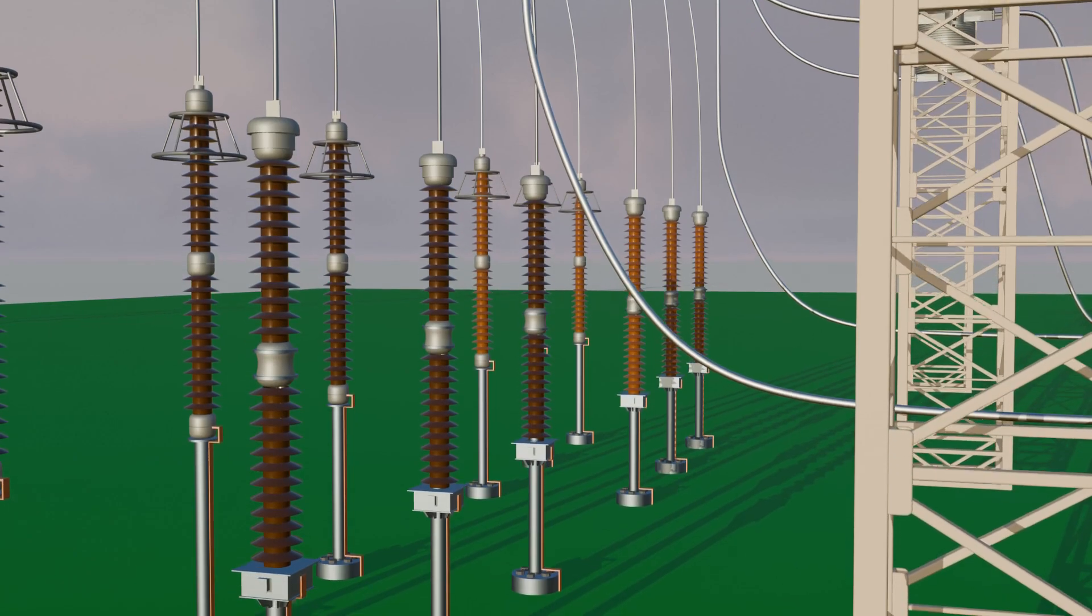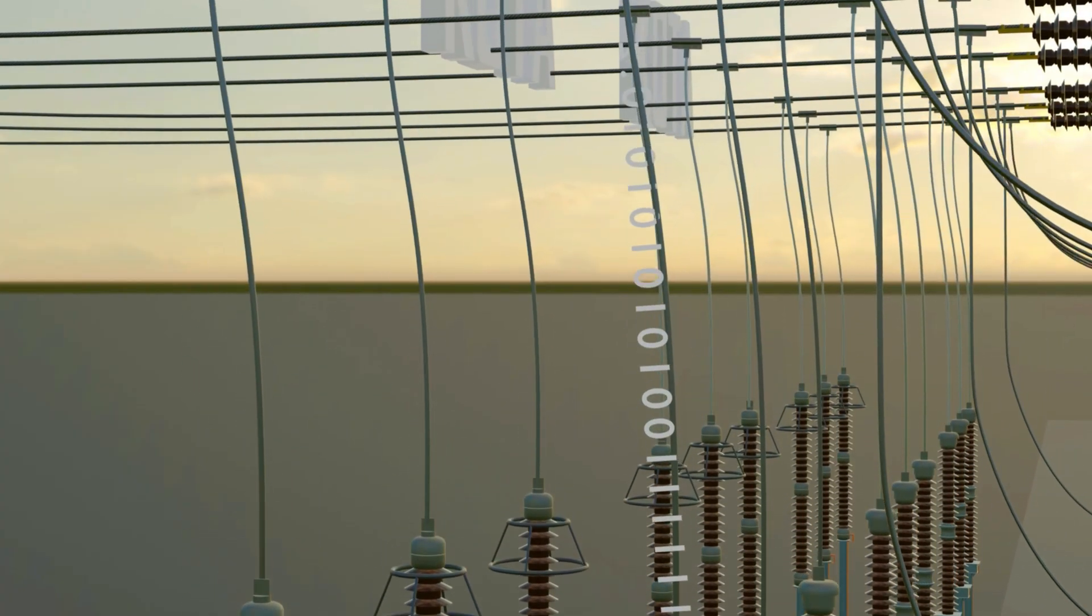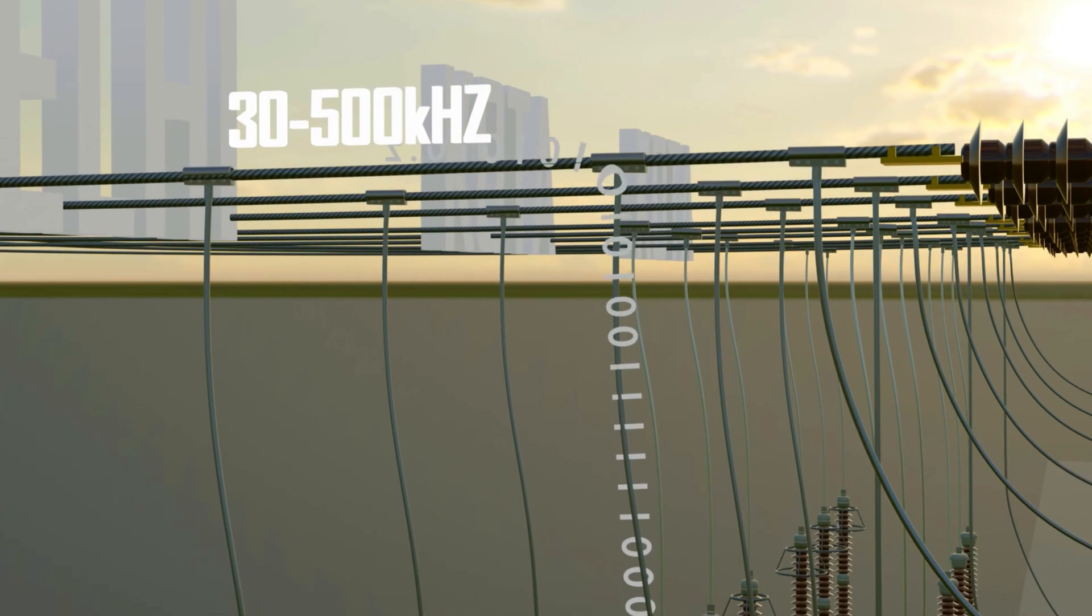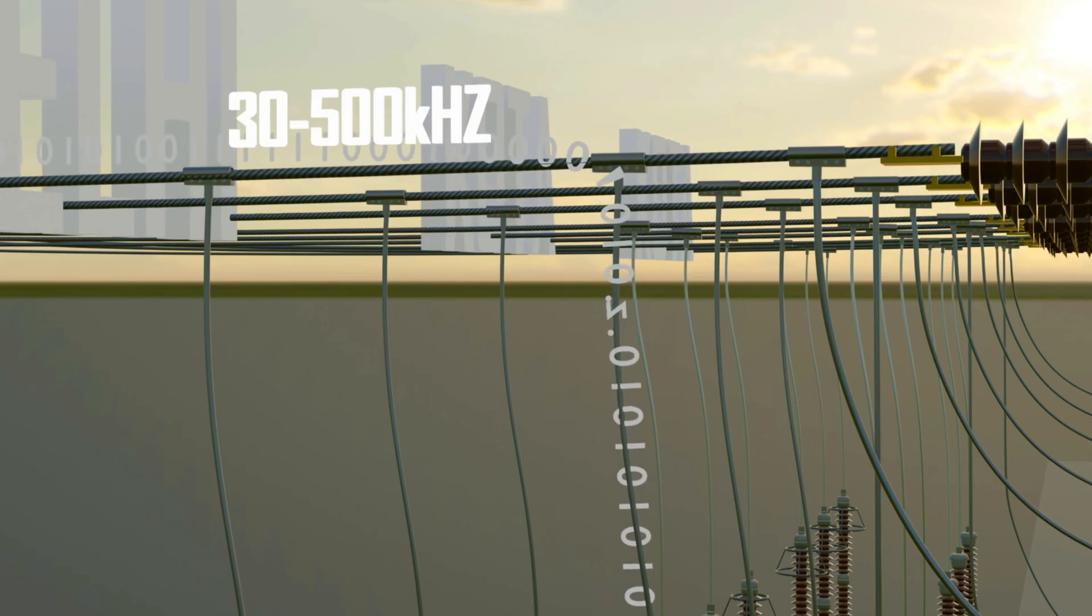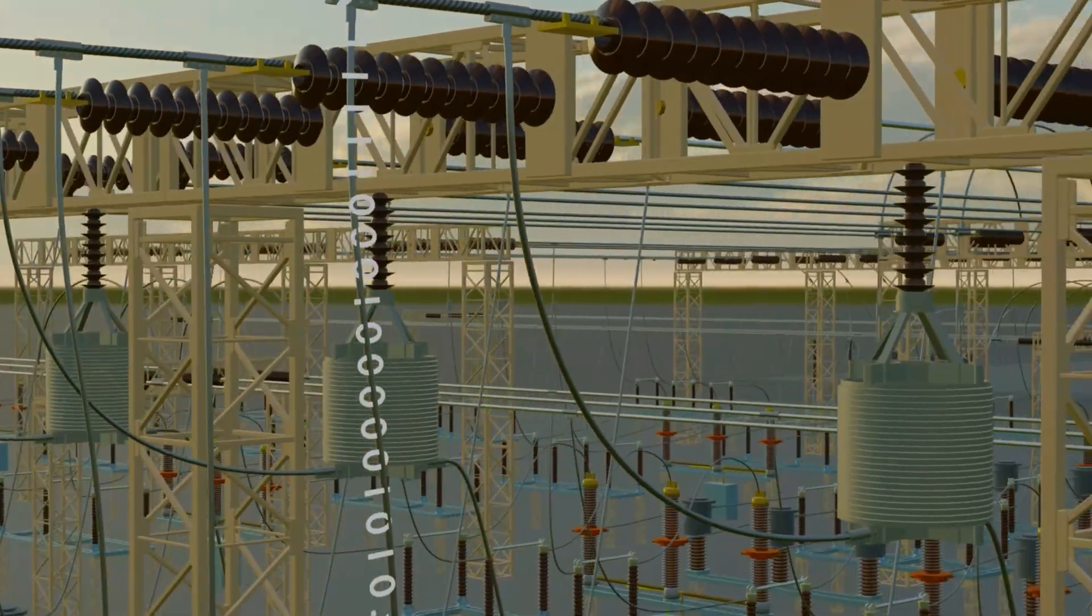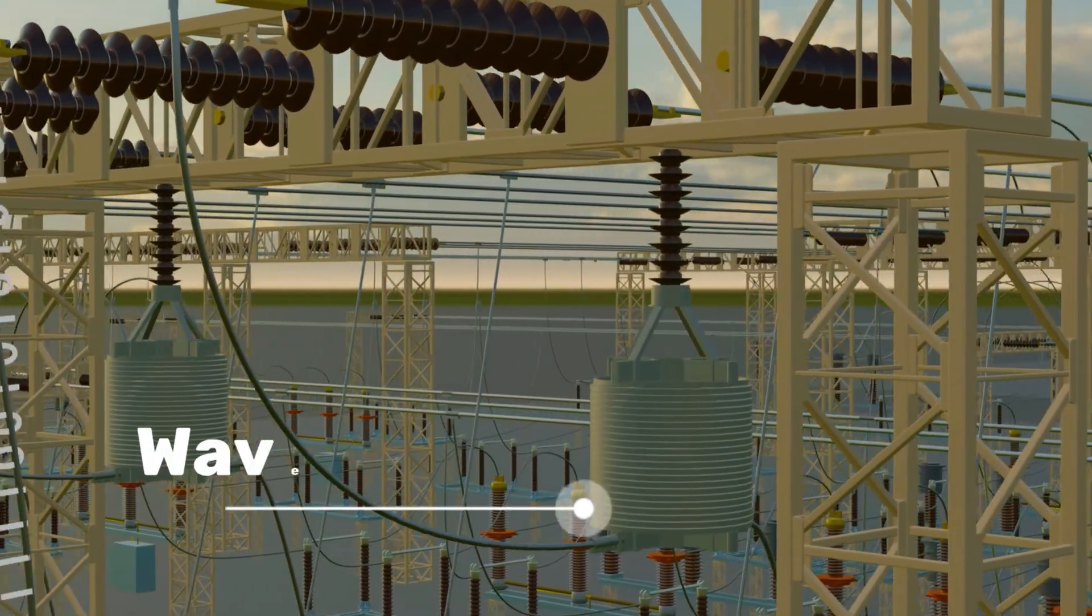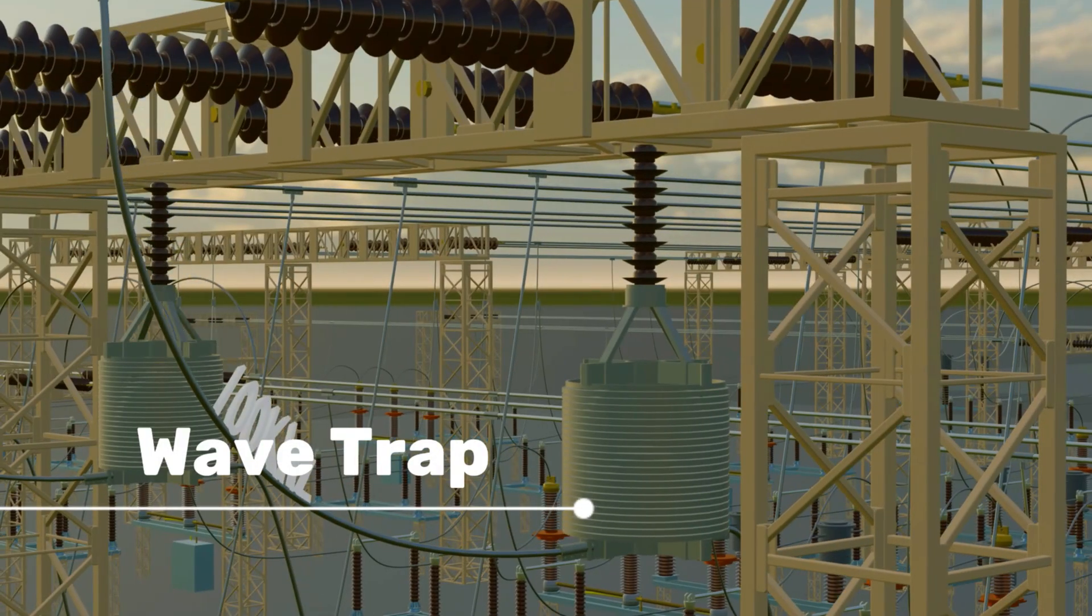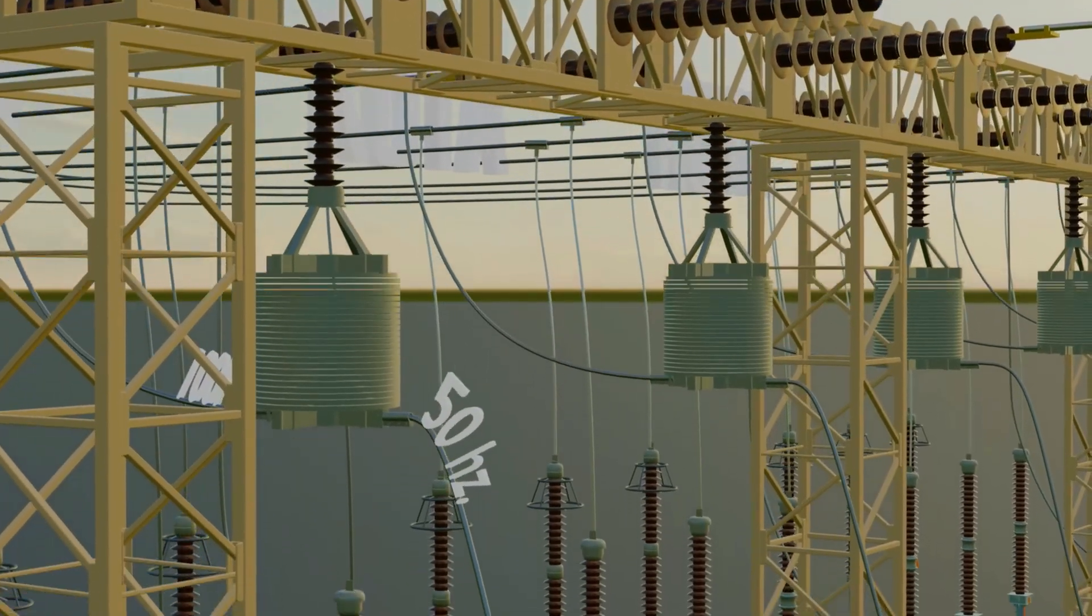Apart from power transmission, the transmission line can also carry communication signals from one substation to another. The CVT injects these high frequency signals into the line and later collects them as well. But we only need 50 hertz power frequency in the line, so a wave trap blocks the high frequency communication signals and allows only the 50 hertz power to pass ahead.